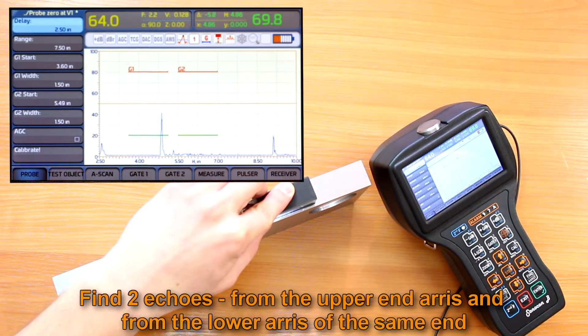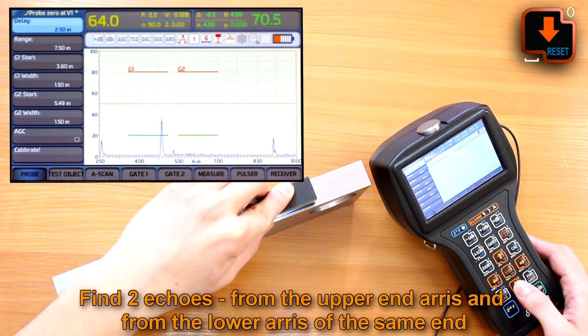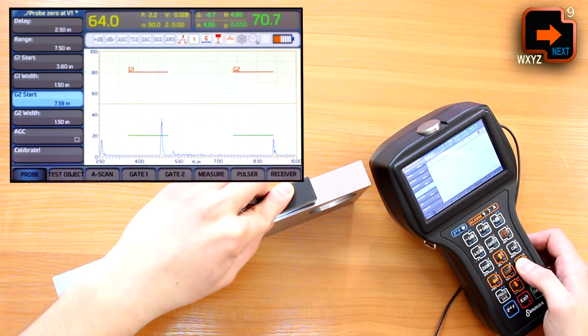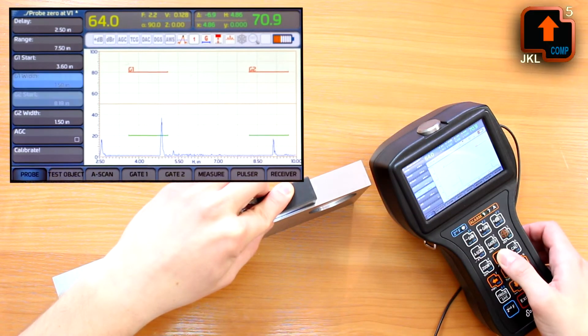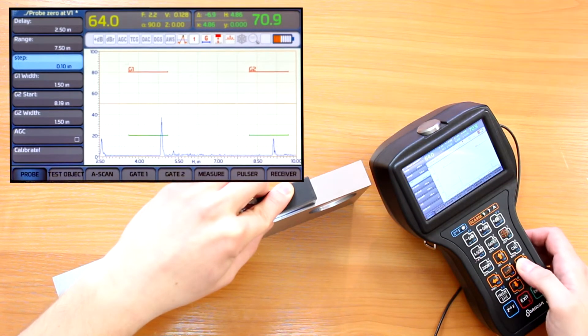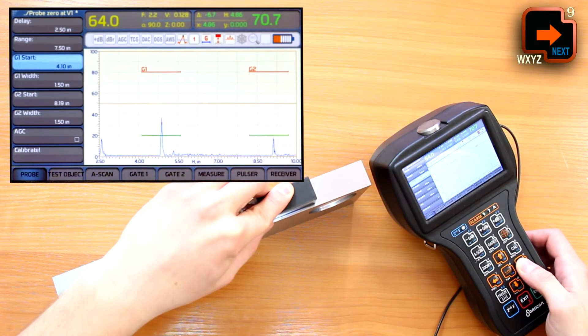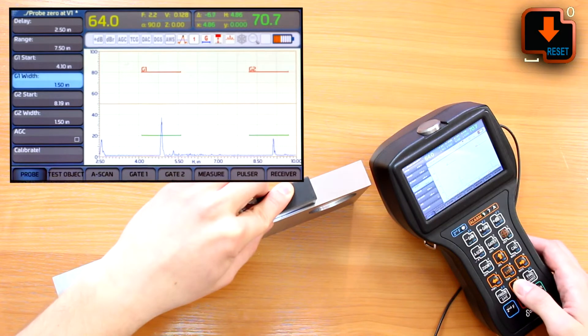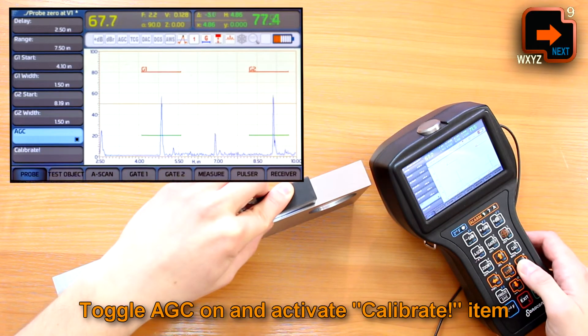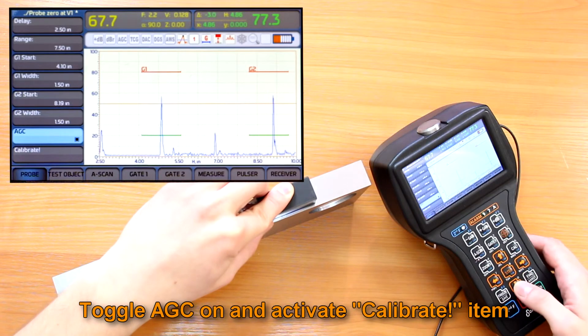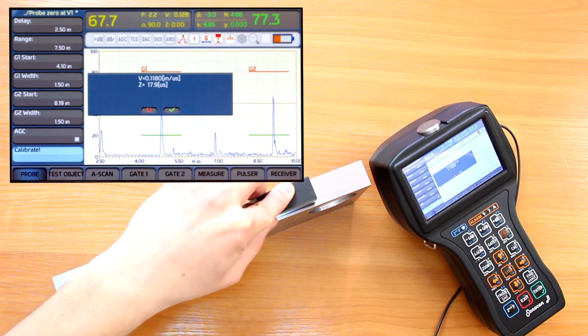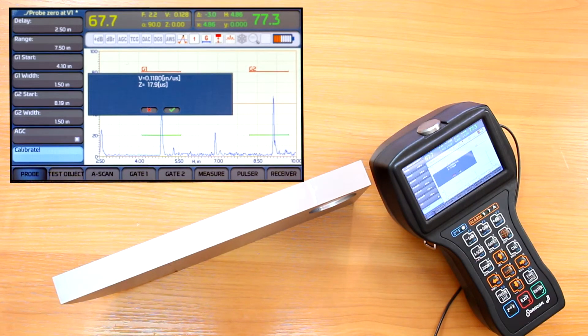I place my probe on the upper edge of the V1 and ensure good acoustic coupling. We can see two echoes — the first from the upper end arris and the second from the lower arris of the same end. I gate those signals with two gates, toggle AGC on, and activate the calibrate item. The device shows the calculated values of sound velocity and probe zero. We confirm with the enter button.